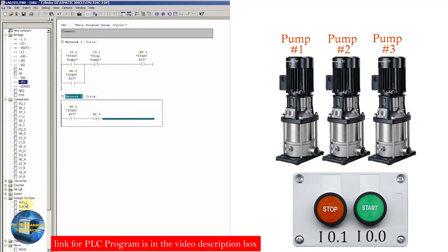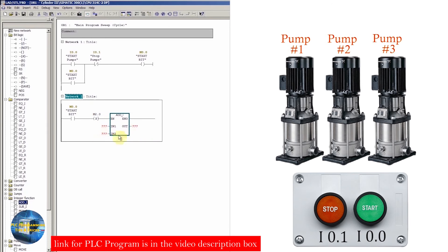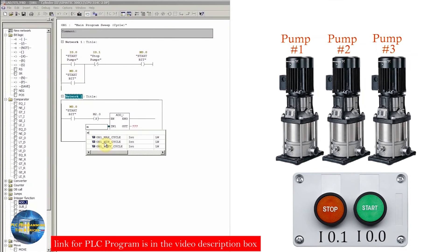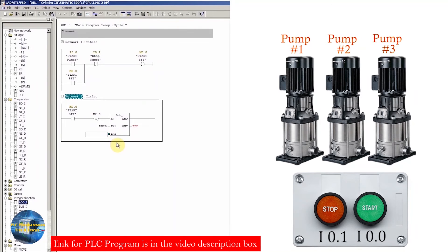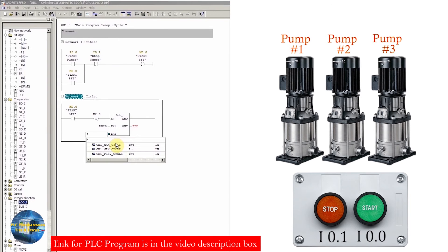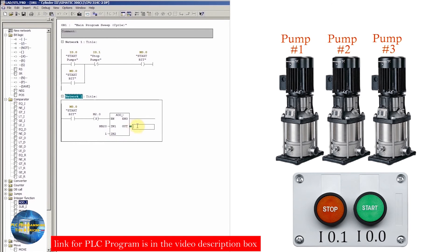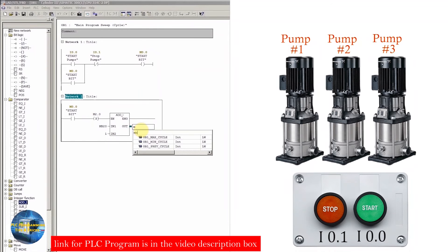Next, we will insert an ADD integer function. This function has two inputs and one output — it adds the two input values and saves the result in the output address. In input 1 we will write MB20 (memory byte 20). In input 2 we will enter 1. And in the output we will enter MB20 again.